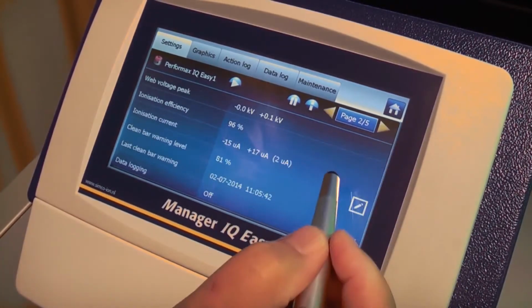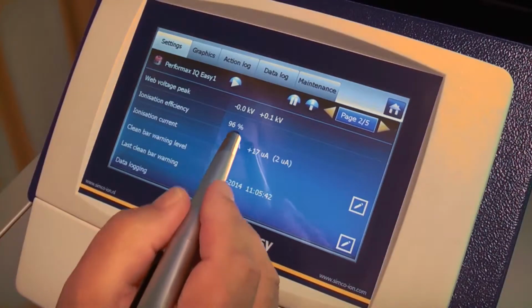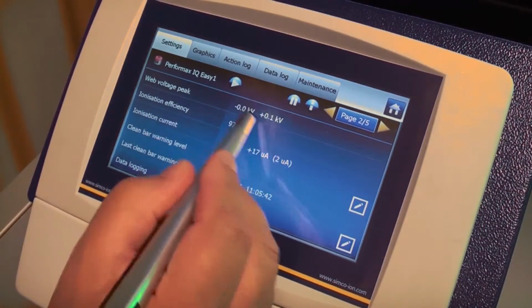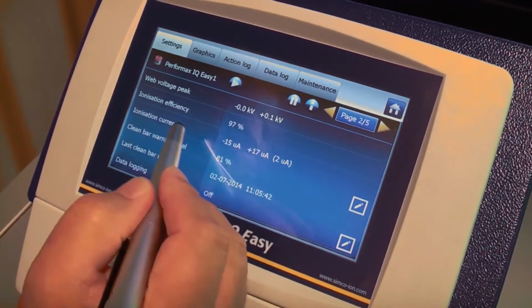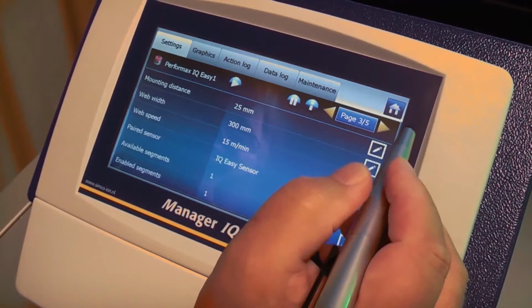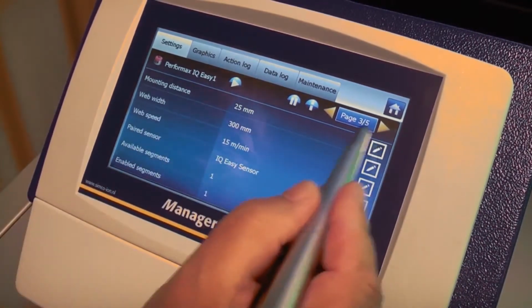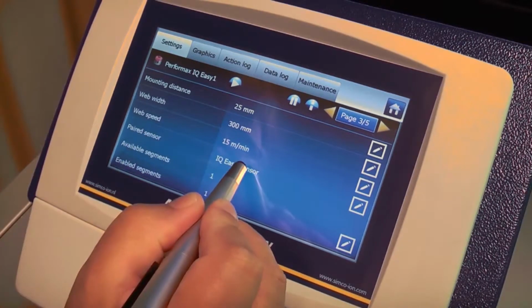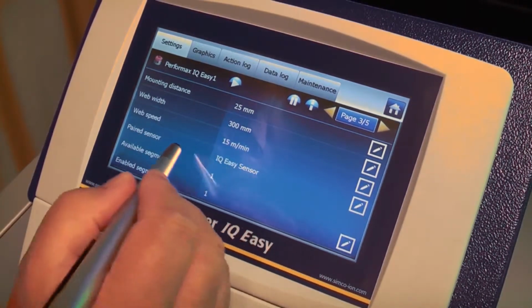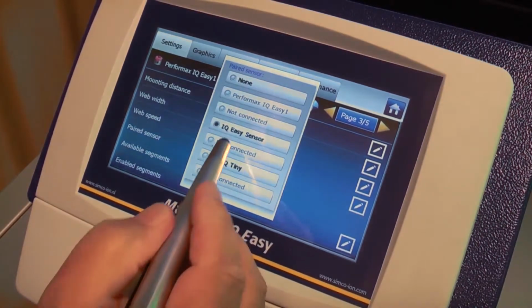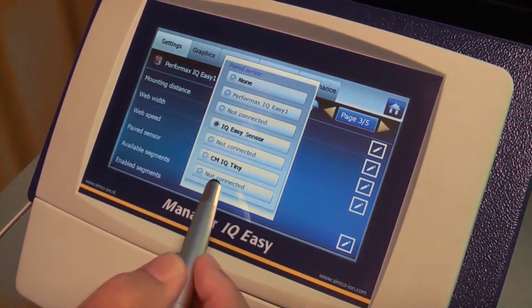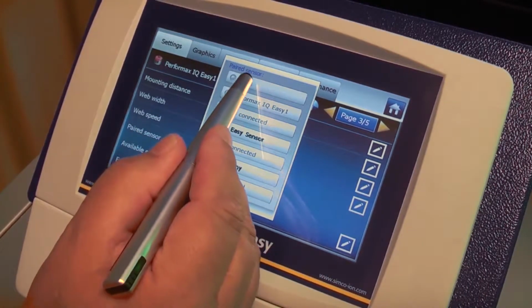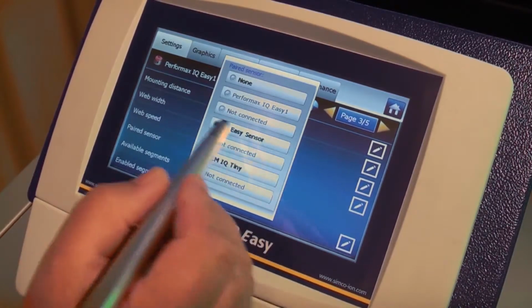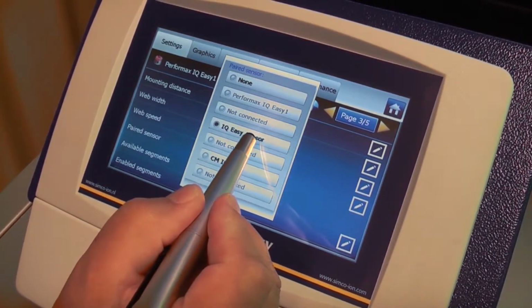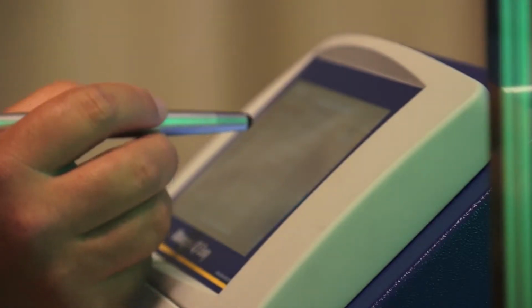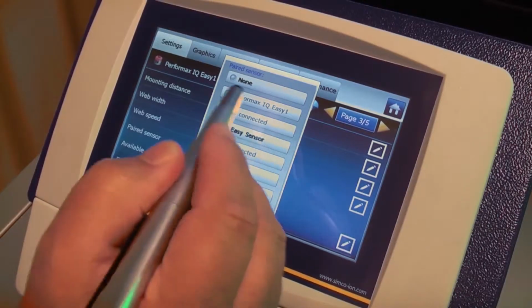On the next page, you will have the web voltage peak. It will show it now when there is a sensor attached. At page 3, we'll have to let the bar know from which sensor it will have to take its data. So here you will get a list of all the connected devices. If this is set to none, there is no connected device. In this case it has been set to IQ Easy Sensor. It means the sensor is giving the static bar data for the closed loop feedback.